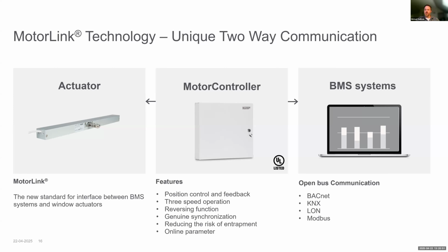There's a 3-speed operation system where it also produces sound level differences with those 3 speeds. The faster it gets, the louder it gets. But if you're at the lowest speed, it's almost silent. You can hear the seals break on the windows, but it's almost entirely silent. There's a reversing function and the genuine synchronization between all motors within that control panel and the BMS system. And to have that done, it's usually done through an open bus communication, which is typically BACnet, KNX, LON, and Modbus from the BMS system, which then you can find more parameters within the BMS system to control when the window's open, what zone is opening, what zone should be closed, and all of those parameters.